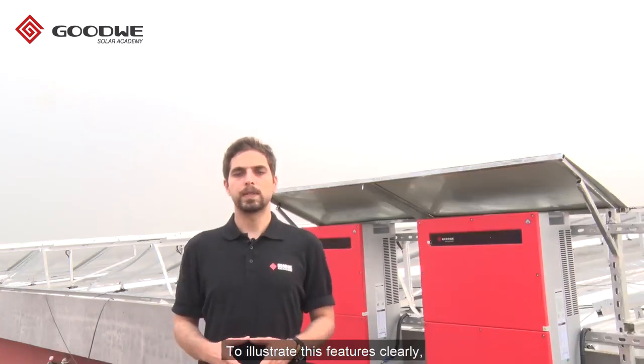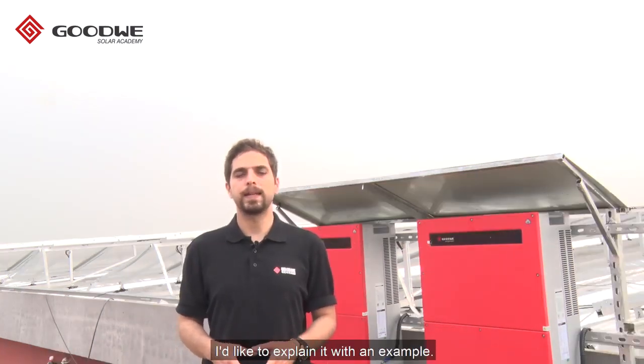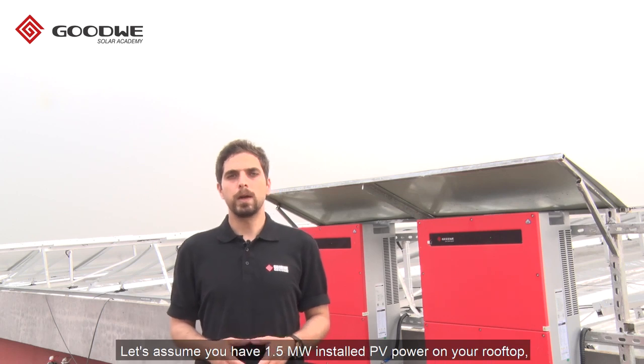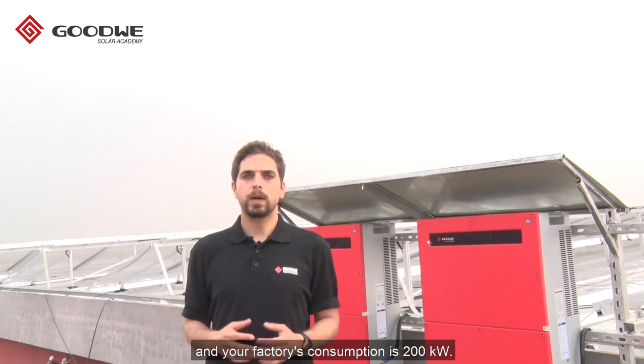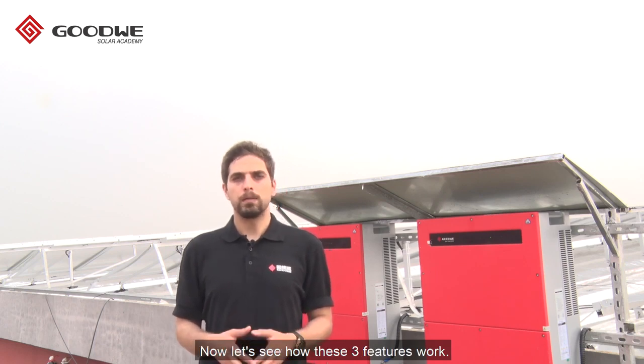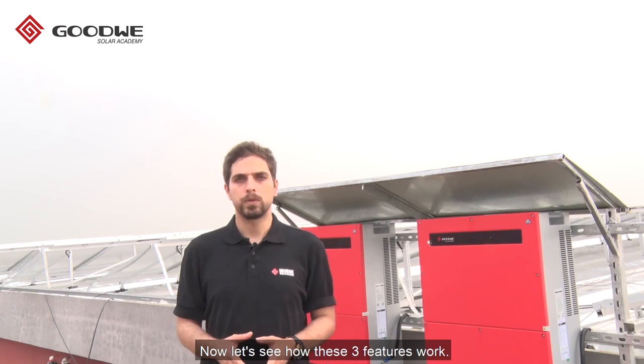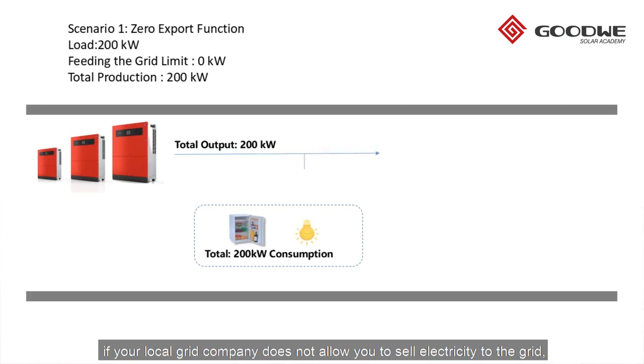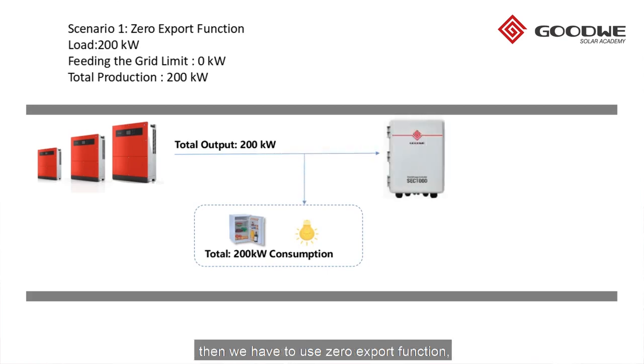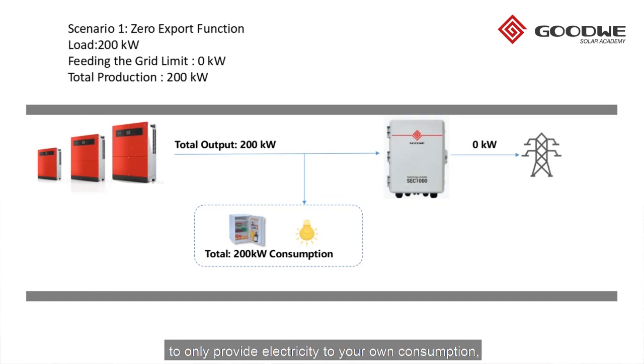To illustrate these features clearly, let me explain with an example. Let's assume you have 1.5 megawatt of installed PV power on your rooftop and your factory's consumption is 200 kilowatt. In the first scenario, if your local grid company does not allow you to sell electricity to the grid, then we have to use the zero export function. The inverters will reduce production to 200 kilowatt to only provide electricity to your own consumption but won't feed the grid.